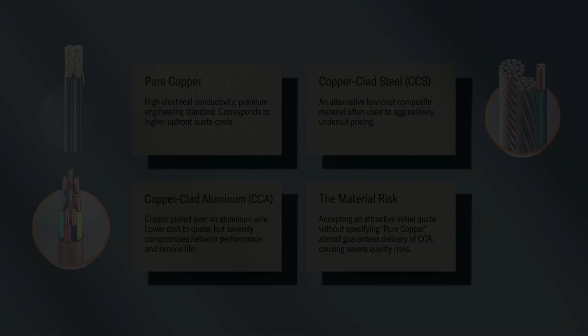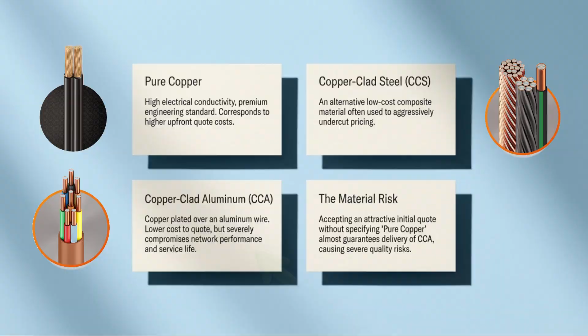The core of a cable lies in its internal conductor material. Common materials on the market include pure copper, copper-clad aluminum, and copper-clad steel. Pure copper cables have better electrical conductivity, and their corresponding costs are also higher. Copper-clad aluminum involves plating copper on the outside of an aluminum wire, which has a relatively lower cost, but compromises on performance and service life.